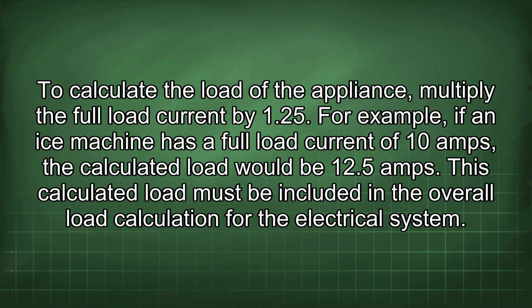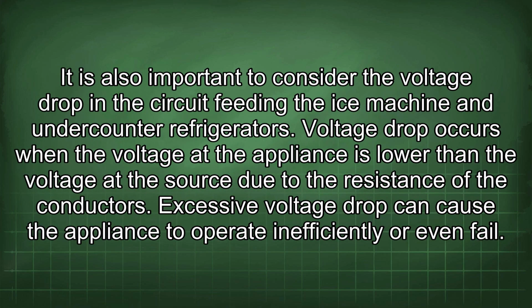For example, if an ice machine has a full load current of 10 amps, the calculated load would be 12.5 amps. This calculated load must be included in the overall load calculation for the electrical system. It is also important to consider the voltage drop in the circuit feeding the ice machine and under-counter refrigerators. Voltage drop occurs when the voltage at the appliance is lower than the voltage at the source due to the resistance of the conductors. Excessive voltage drop can cause the appliance to operate inefficiently or even fail.